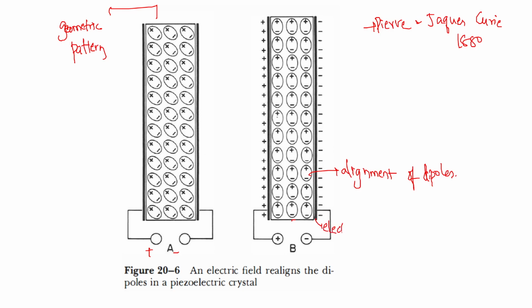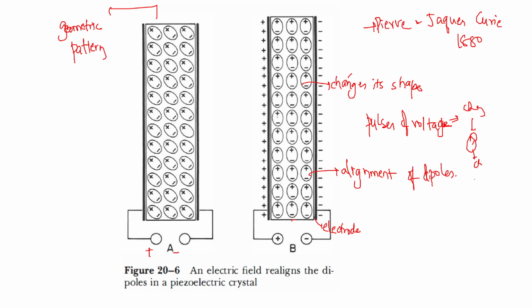So these two are electrodes. When electricity is passed between the two electrodes, a charge will pass through this piezoelectric crystal. When voltage is applied across the piezoelectric crystal, it will change its shape. So in the piezoelectric effect, there is a change of shape. If the voltage is applied in pulses, then first there will be a change of shape, and again it comes back to normal, again change, again normal. That means this change in shape and coming back to normal will result in production of a sound pulse.